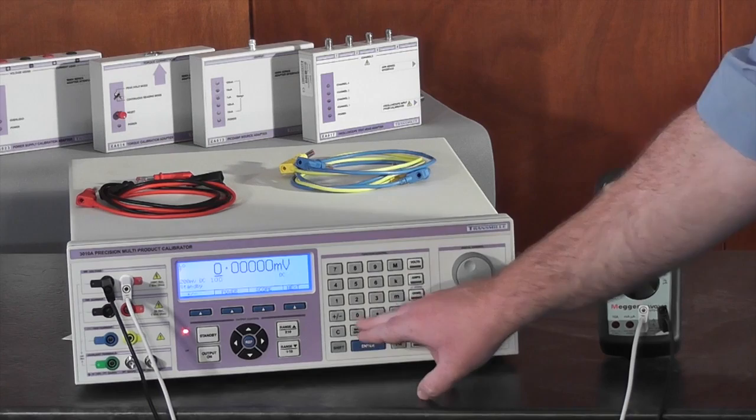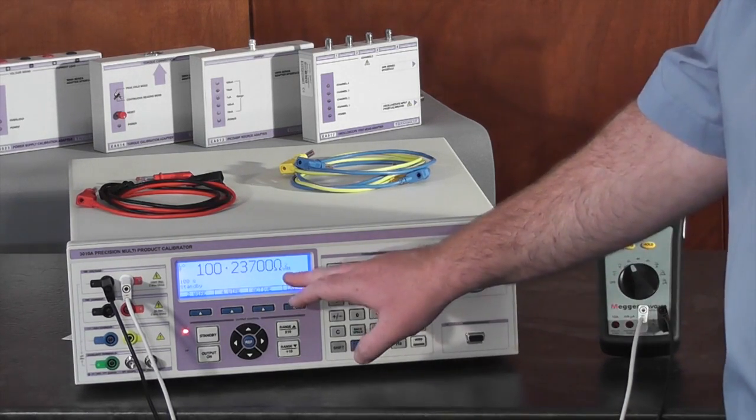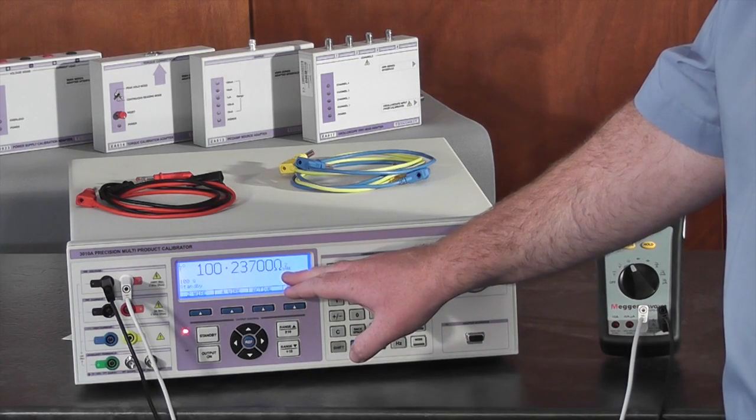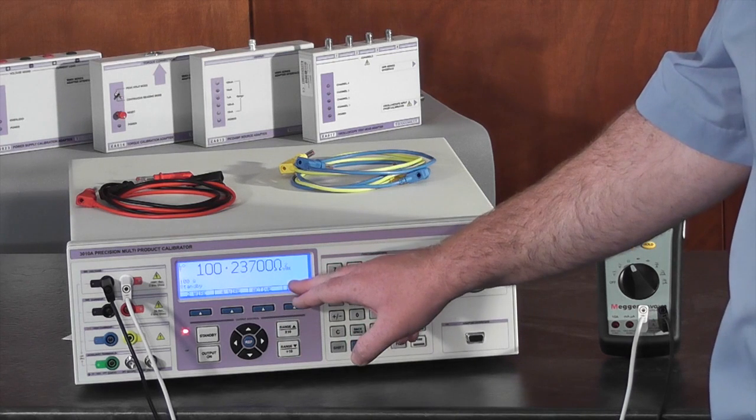The calibrator defaults to 2 wire ohms output. As you can see, the output is not exactly 100 ohms. This is due to the value being a true resistor.